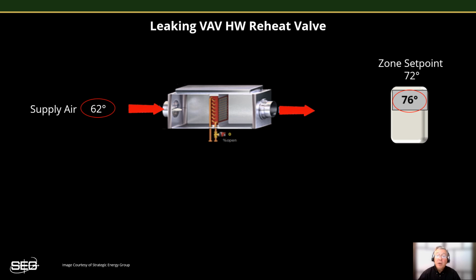A quick check of the air handler's supply temperature, and we see that it's sending 62-degree air out to the terminal box, which appears reasonable for the current outside air conditions. Next, we check the reheat valve command to see what it's doing, and we see that it's being commanded closed at 0%, which sounds correct since the zone is above set point. Looks like it's time to head out to the zone and see what's going on out there.